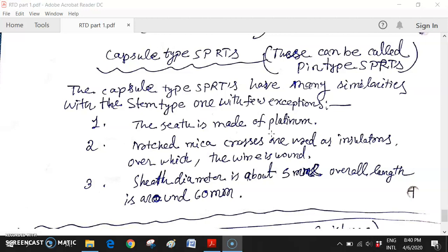This filling with dry gas is necessary to avoid insulation leakage through the release of moisture from mica. This is common for both capsule type and stem type SPRT. As mica is used for insulation, the coil is wound on the mica insulation, and due to some reaction whenever it is heated, some moisture can come from mica - that's why dry gas is very much required inside.